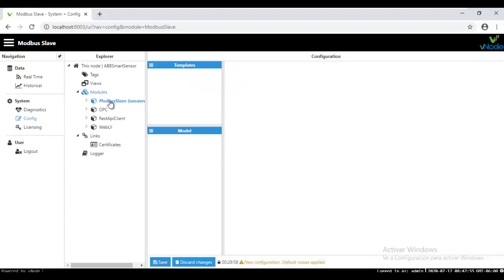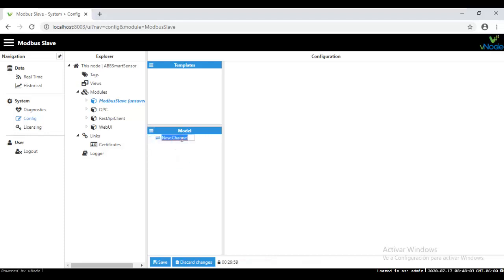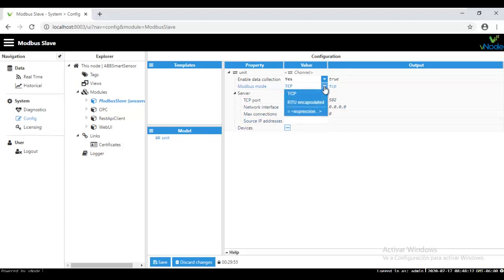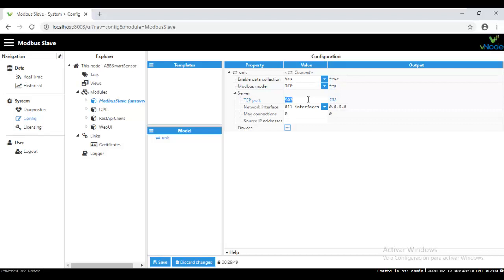To start configuring the model, first of all, you need to create a new channel right here. I'm going to put it like a unit. And then under Modbus Mode, you are going to select TCP or even RTU encapsulate. I'm going to use the TCP mode, which is also the port number will be the predefined or the standard port for Modbus 502.